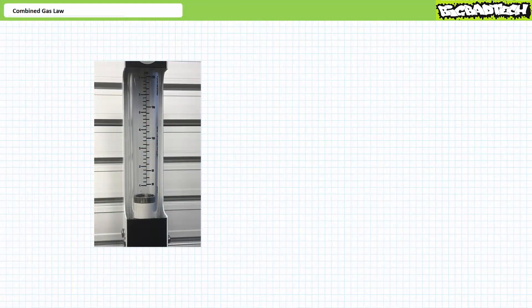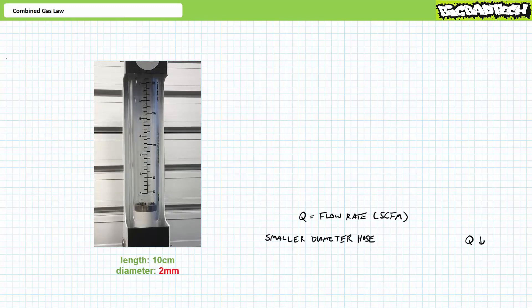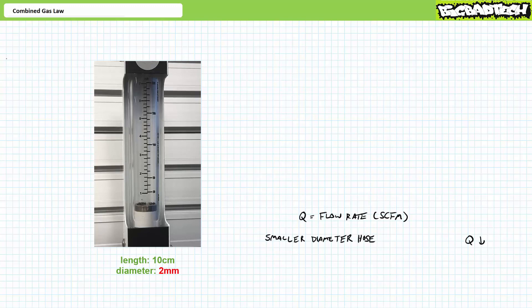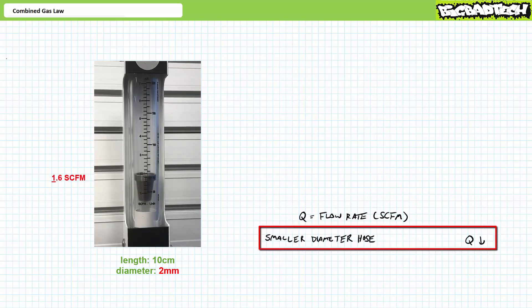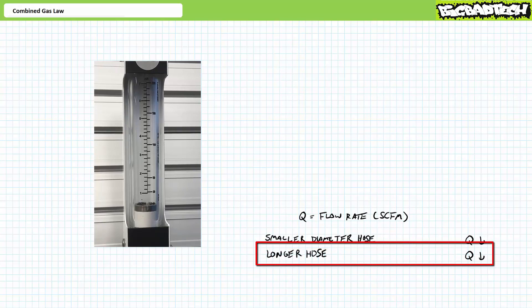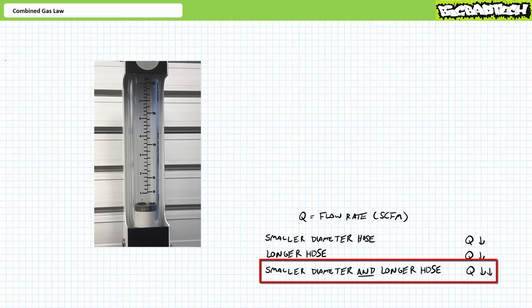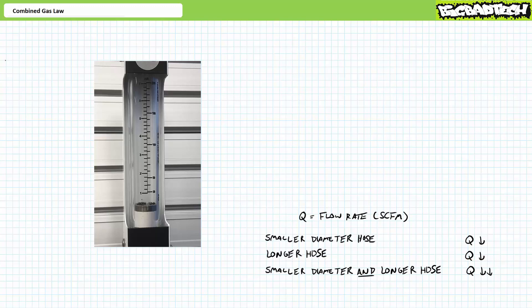Here's a quick demonstration of flow rate measurements. Consider a pneumatic flow meter, schematically represented as kind of a baseball-looking circle. Using a short length of 4-millimeter diameter pneumatic hose, when I crack open the on-off valve, the thimble in the flow meter floats to about 4.2-ish standard cubic feet per minute. If, however, I use the same length of a much smaller 2-millimeter diameter hose, when I crack open the on-off valve, the flow meter indicates flow drops to a paltry 0.6-ish standard cubic feet per minute. One would expect similar effects using a longer length of similar diameter hose. Consider the compounded effects of smaller diameter and longer length hose, such that flow rate is effectively choked off to the tiniest puff of air. Keep hose lengths as short as possible and use reasonably sized large diameter hoses to avoid restrictions in flow rate. Additionally, avoid sharp bends when routing hoses, as these also exhibit detrimental effects to flow.